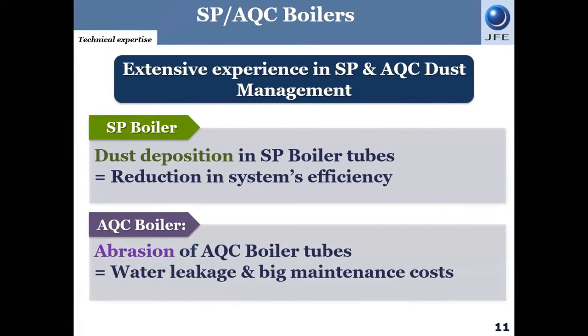Let's see how important this waste heat recovery from JFE is. The SP boiler that we have - basically talking about the conventional design - we talk about dust. It's a big problem especially for the cement industry. It can reduce system performance; slowly your SP boiler tubes will have problems with dust.